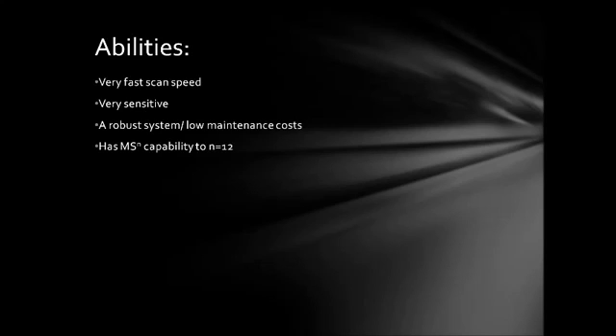The QIT also has the ability to do what's known as MSN, which means you could stack several different techniques of MS or just multiple MSs together. It's actually recorded that you could go to N equals 12, so that would be 12 different mass spectrometry techniques stacked together to yield a better result.